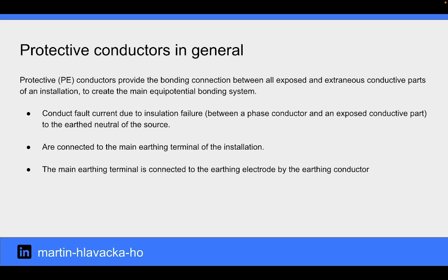Protective conductors provide the bonding connection between all exposed and extraneous conductive parts of an installation to create the main equipotential bonding system. These conductors conduct fault current due to insulation failure to the earthed neutral of the source. PE conductors are connected to the main earthing terminal of the installation. The main earthing terminal is connected to the earthing electrode by the earthing conductor.